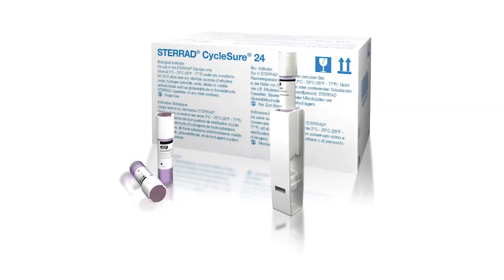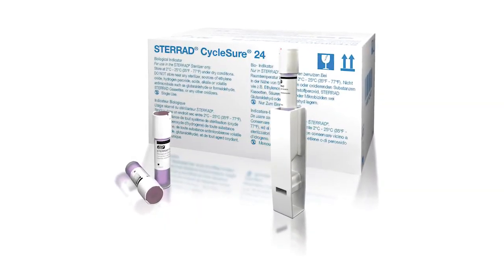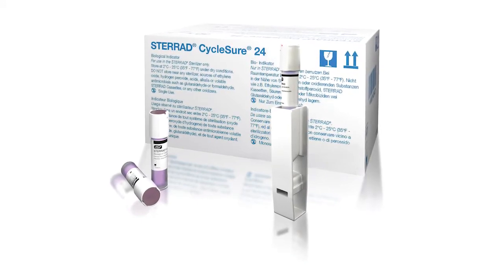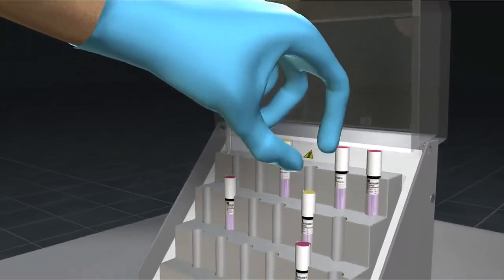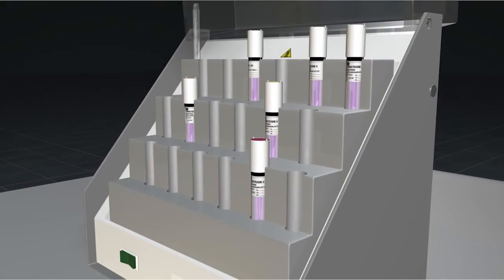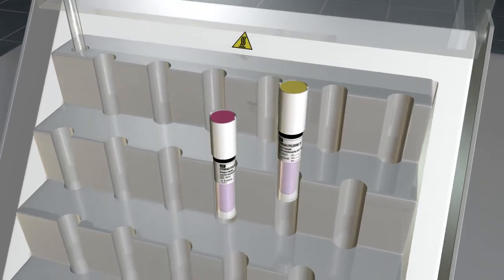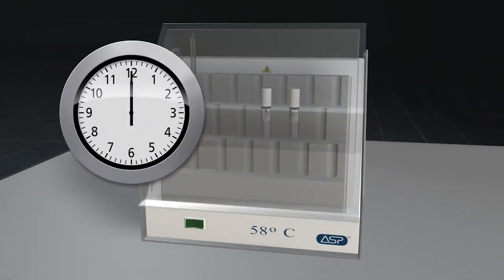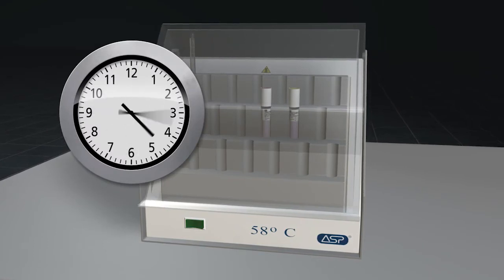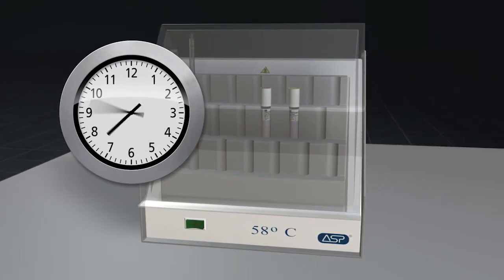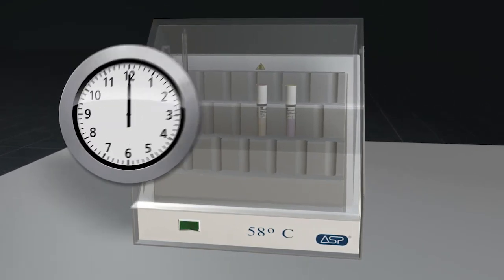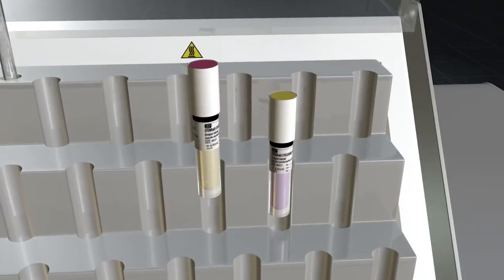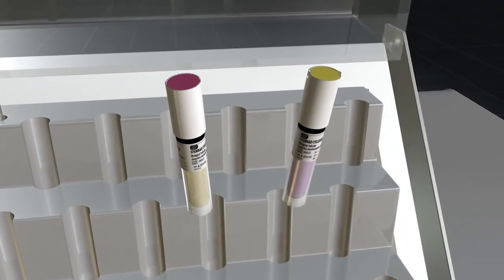Let's review how to process a STERRAD CycleSure 24 biological indicator. BIs are intended to be used as a standard method for frequent monitoring of your sterilizer. To maintain the highest patient safety, ASP recommends monitoring each sterilization cycle with a biological indicator. Follow your hospital or healthcare facility's policies and procedures, national standards, and professional association recommendations for monitoring frequency of sterilization equipment.